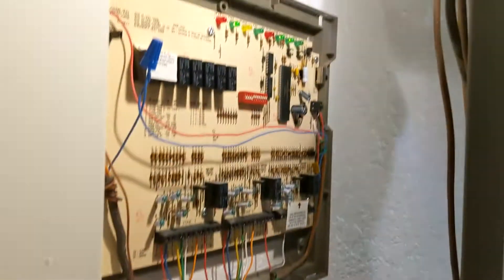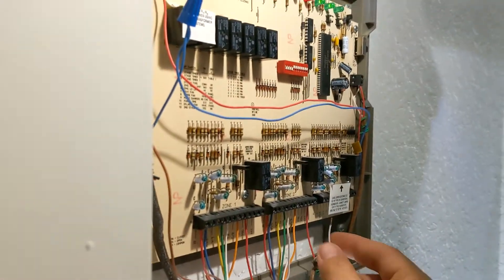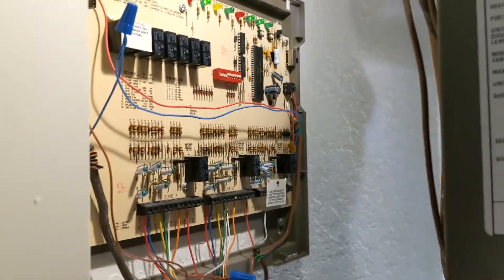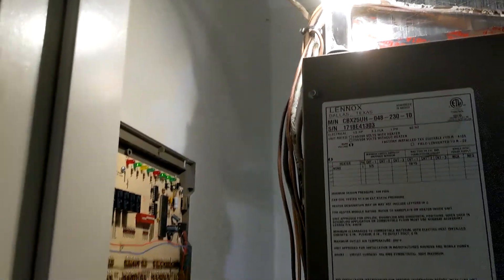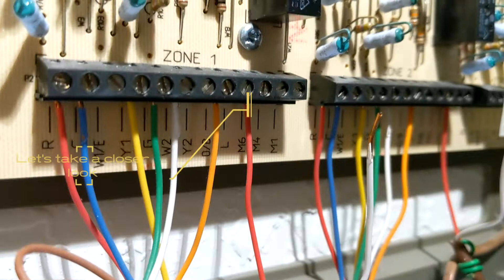So until I get a new zoning board, this is a good way to bypass it. You just remove the power to both dampers that you have, and they open up wide open, so now your unit won't freeze up.